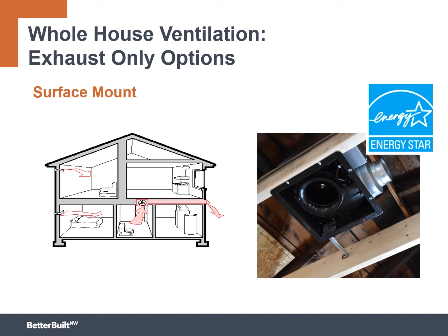Some of the benefits of Energy Star fans are not just that they use less energy. They're typically rated for between 10,000 and 20,000 hours of continuous operation, and they're rated to be quieter. So if you're going to use an exhaust-only strategy, meaning you're going to leave an exhaust fan running all the time or on and off a lot throughout the day, you want the quietest fan that's cost-effective to buy, so people don't turn it off.